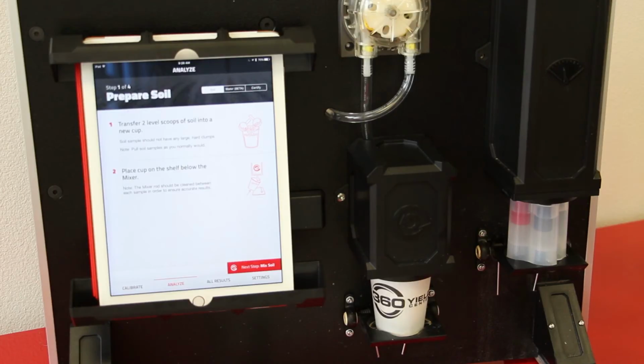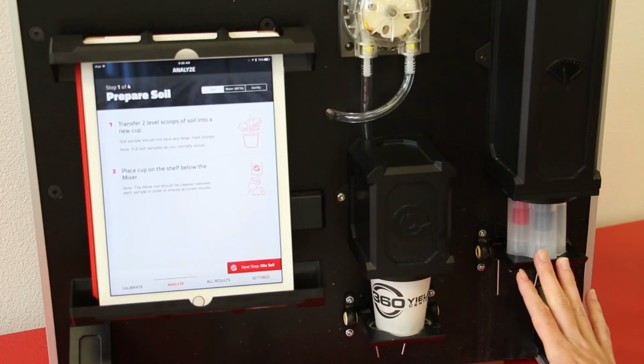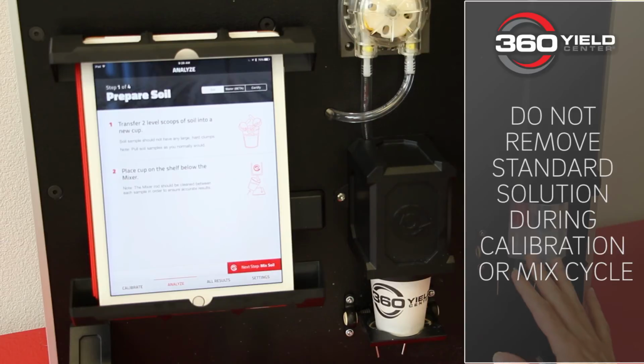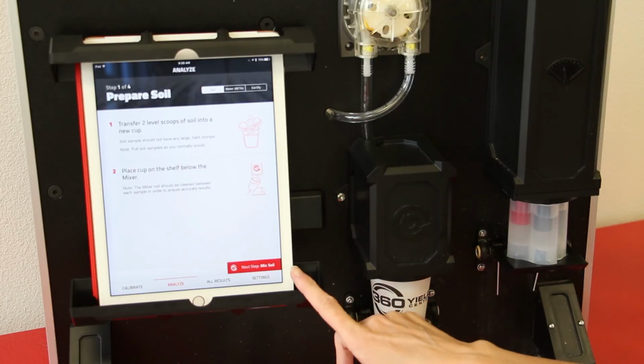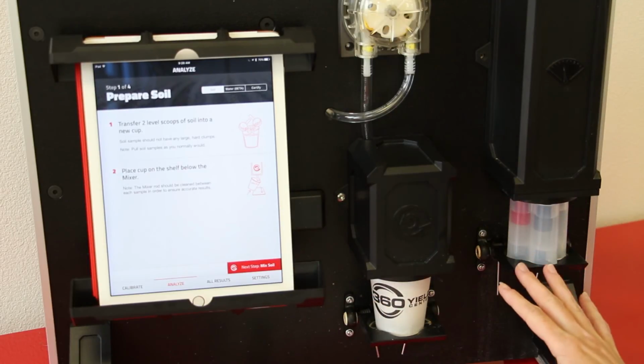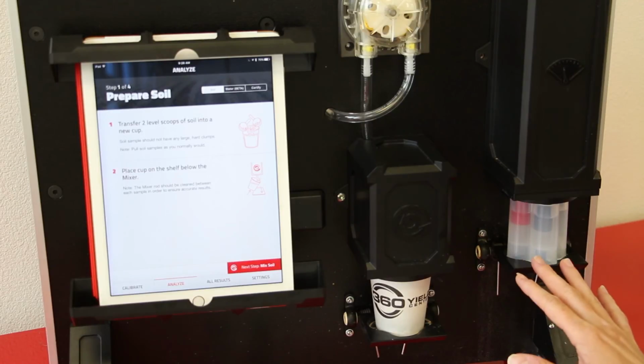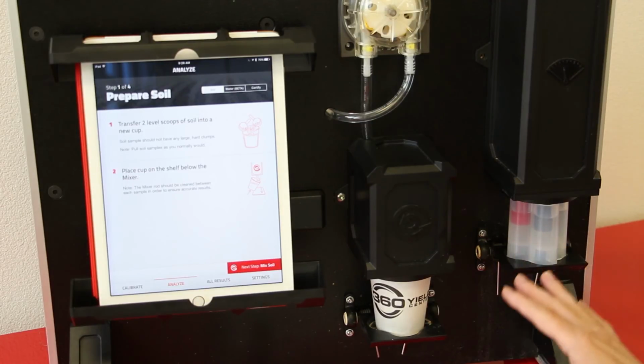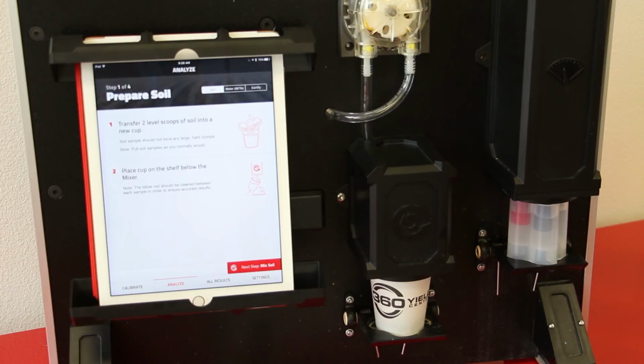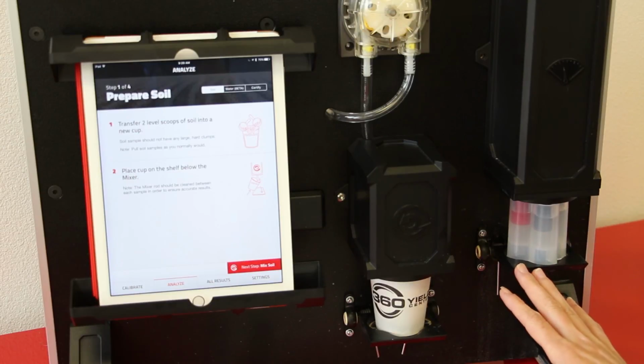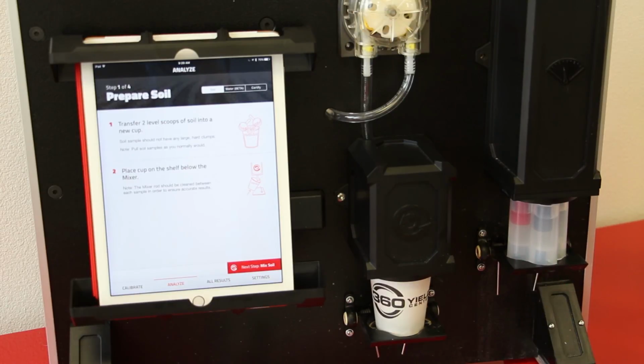And now when we're there, we want to leave on our standard solution that's in the 4-chamber bottle, because it's essential that your sensors are soaking in this 4-chamber bottle while you're running your soil test, because each time we press this mix soil button to begin our mixing process, our sensors are actually recalibrating themselves in the standard solution. So when you don't have your standard solution on but you're running a test, you're going to get an error message. So it's absolutely essential to leave on your standard solution in your 4-chamber bottle while you're running through the mixing stage on the analysis page of that.